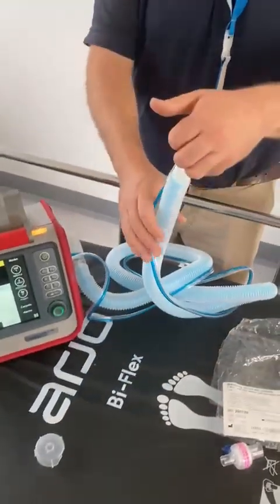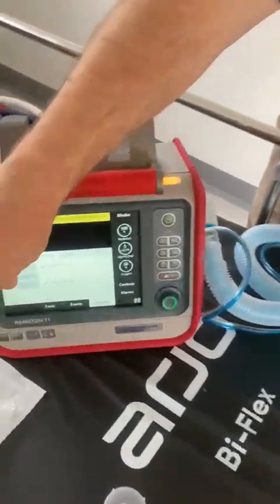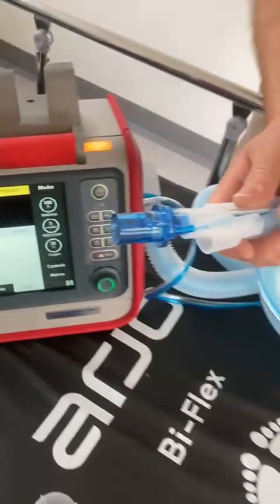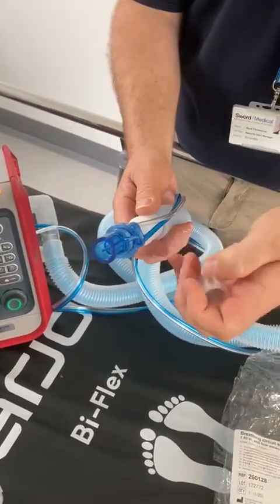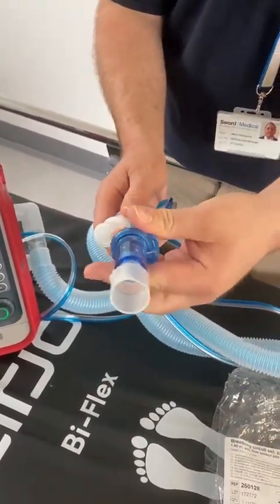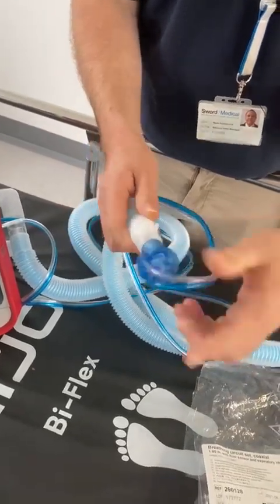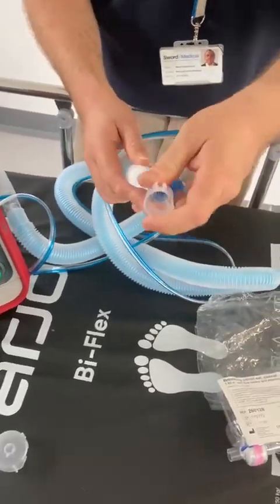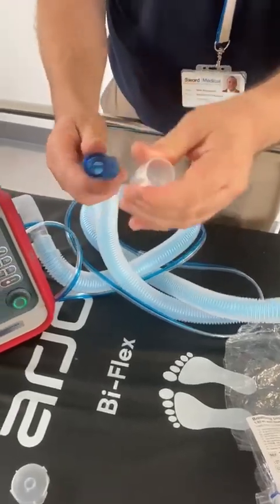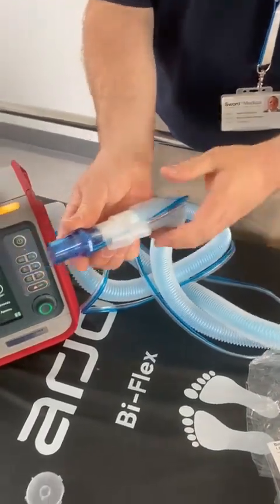Okay, so the next test I'm going to do is my flow sensor, and here's where I'm going to use this little adapter. What the adapter is going to allow me to do is to push it in, take off the flow sensor, turn it backwards and plug it in backwards. It's the only time you use it, during the calibration. Each circuit comes with your adapter mounted here on the circuit.